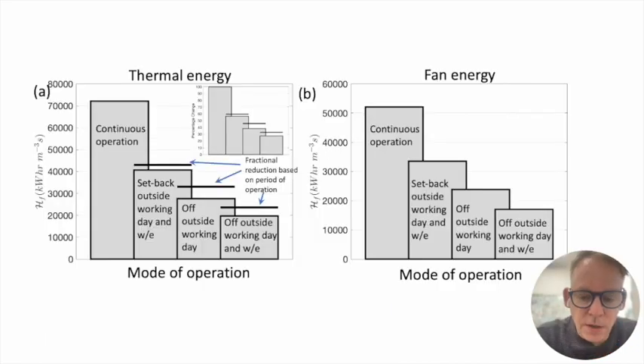HTM 03 requires that the theatre is put in setback operation when not in use. Most theatres, in our experience, are really not in that position at the moment, although they're mandated to do that. If we do put things in setback operation, typically it's not like your television, it tends to go down, the airflow rate tends to go down by 50% because the fan usually has a fixed blade angle, and so has some instabilities below about 40% of the typical speed of operation. But that reduces the energy cost by about 40%.